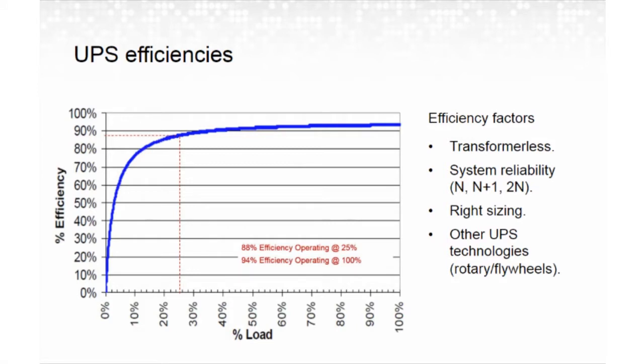If you put in, say 10 years from now, you know what your load's going to be, and you put in a 1,100 kW UPS, but for the first 2 years, you only operate at 20%, you're going to be operating way low on the curve and very inefficient. So you want to make sure as you size it, so that you right-size the equipment as you go. You want it to be higher on the efficiency curve.